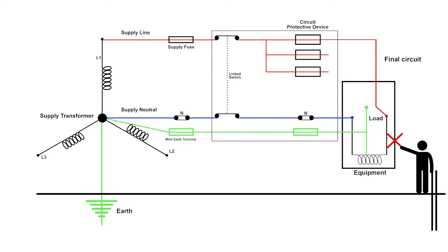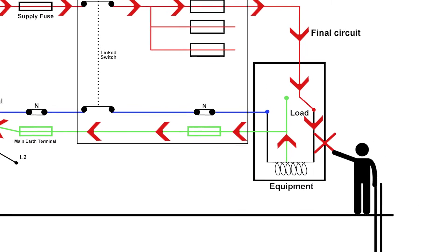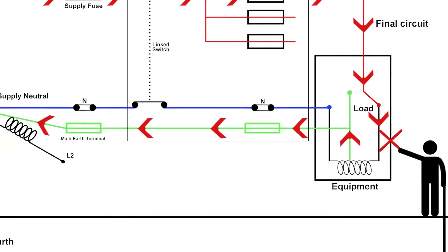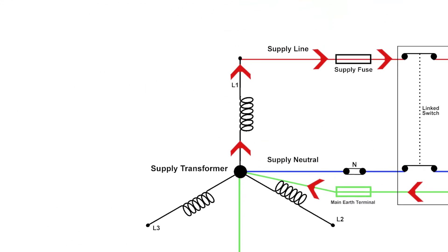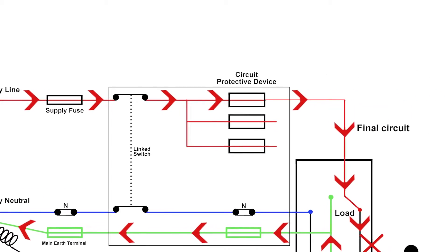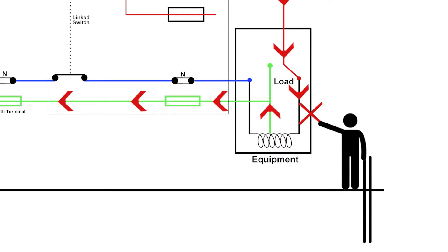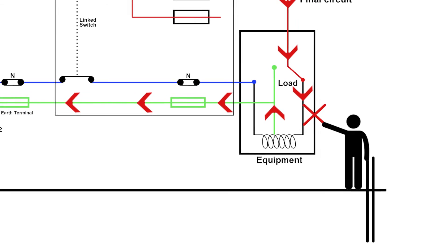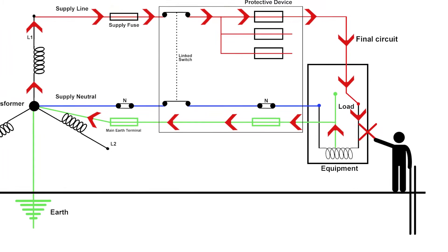You can see that in the event of a fault, the current's going to flow through the case of the machine to wherever our earth is connected to, then through our earthing system back to the star point of the transformer and it forms what we call an earth fault loop. In other words, for us as electricians, we'd call that our ZS. And we need to know that the value of that ZS is low enough to operate that protective device.